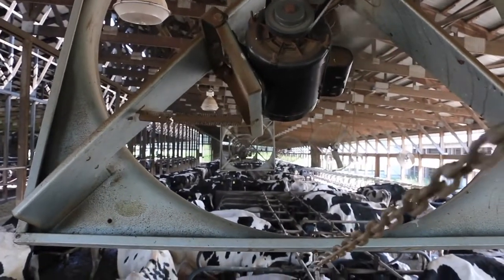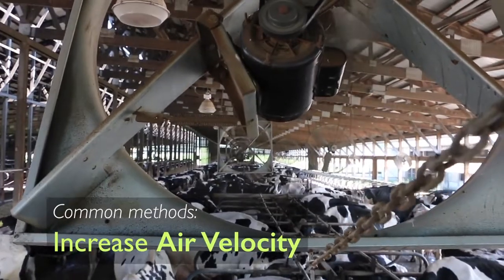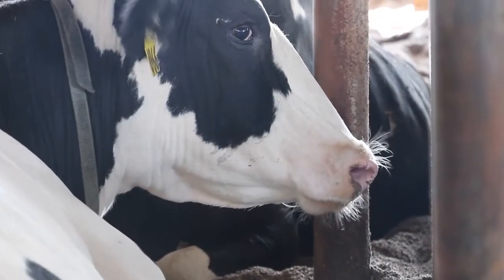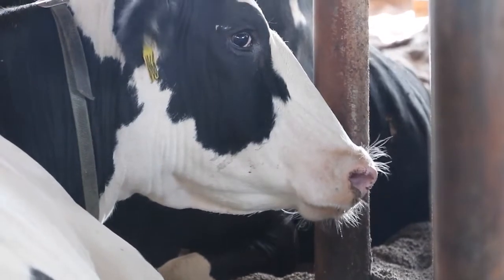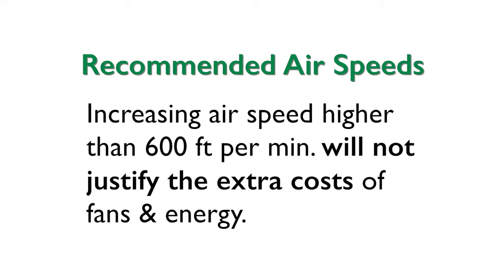Another commonly used method to cool animals is to increase the air velocity, or air speed, moving past them. This helps increase both convective and evaporative cooling. Usually air speeds between 300 and 600 feet per minute are recommended. Increasing air speed any higher than that will not improve the cooling enough to justify the extra costs of additional fans and energy used.